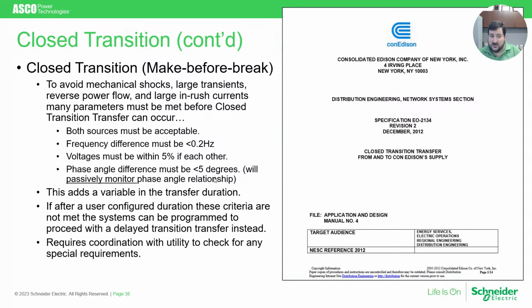We are not controlling or doing synchronization with the equipment, but the thing is that generator frequencies tend to be slightly higher than utility frequencies. For example, operating at 60.1 hertz versus 60 hertz, and they will naturally drift in and out of synchronization with each other due to that.